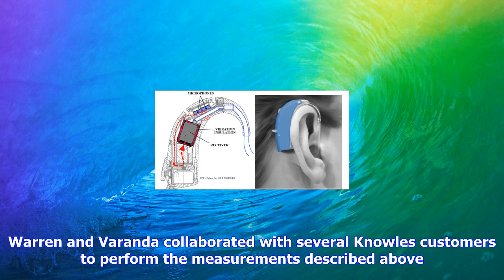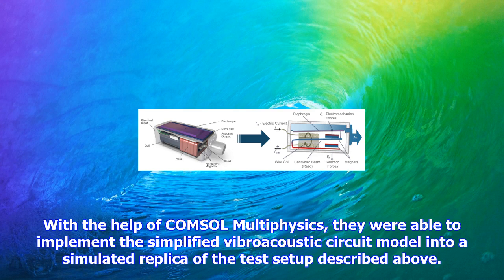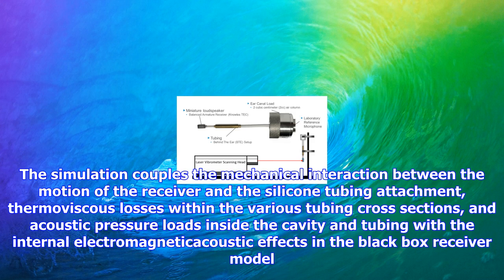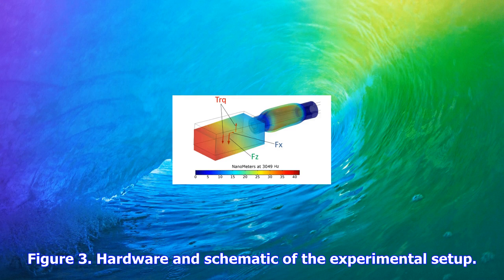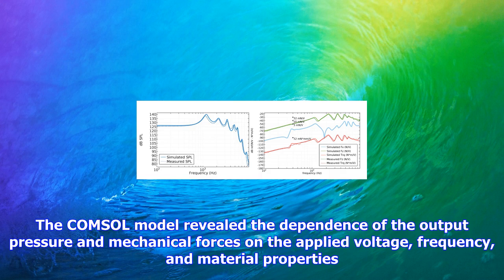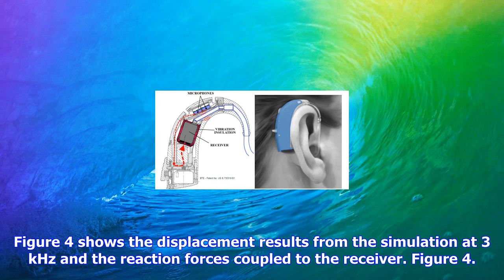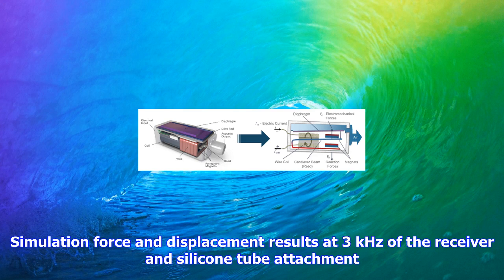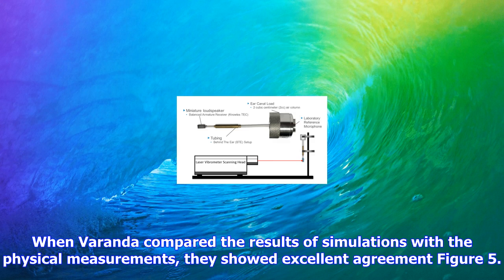Like common hearing aid tests, this test involved connecting a receiver to a short section of tubing leading to an enclosed cavity with a 2 cubic centimeter (2 cc) volume, which is a standardized ear canal acoustic load, as shown in Figure 3. The acoustic pressure inside the cavity is measured with a laboratory-grade microphone. To help verify the robustness of the model, the receiver was also measured using a complex tubing assembly similar to a BTE hearing instrument. The long tubing in this design varies in diameter, and is long enough to support multiple acoustic resonances. At the same time the acoustic output was being measured, the receiver's structural motion was captured by a laser vibrometer. Both translational and rotational motion were measured by observing the motion at multiple points on the surface of the receiver housing. Warren and Veranda collaborated with several Knowles customers to perform the measurements described above.